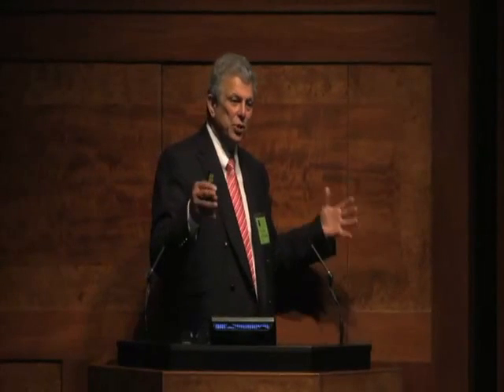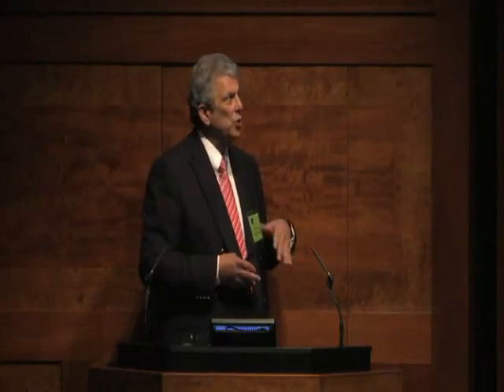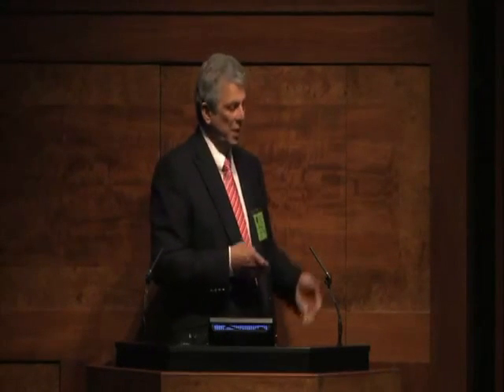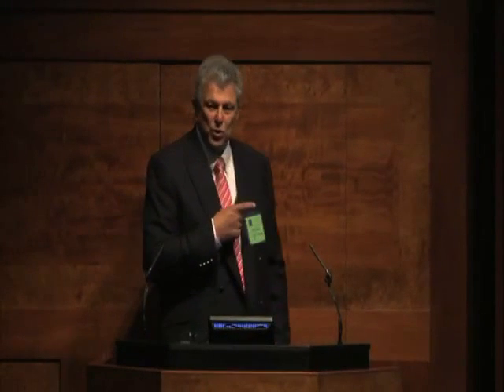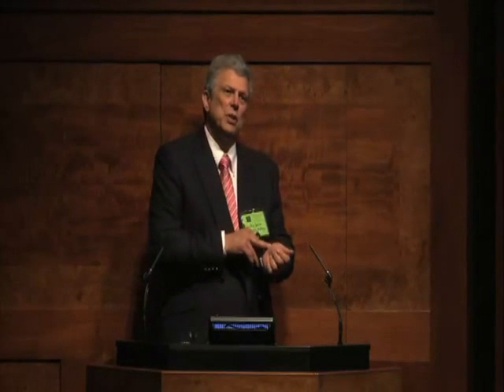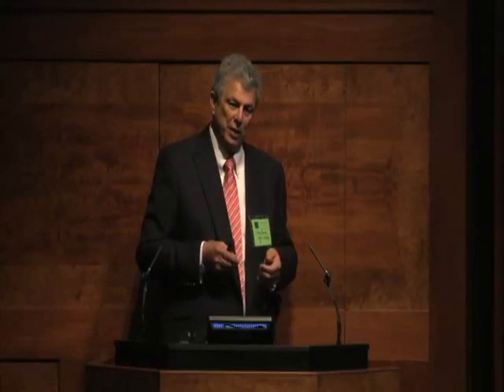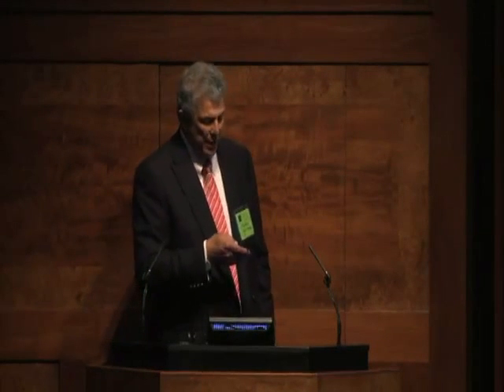So your system is sufficiently large, and you'd expect a system like this to last 25 years. So it's not theoretical, this is a practical example. And we've done this about 2 or 3 times. So it's a technology. What you saw there is producing about 30 megawatt thermal, and that will produce about 3 to 4 megawatt electric. So it's been produced.